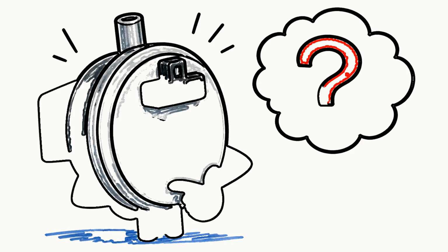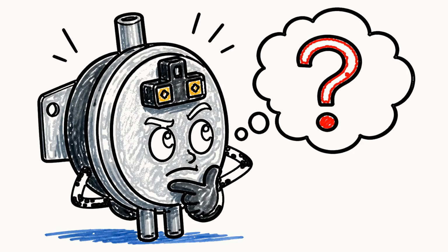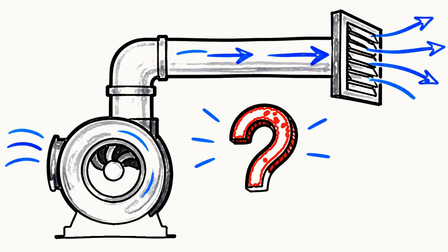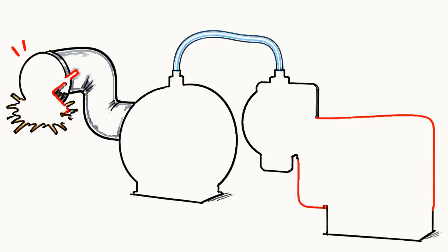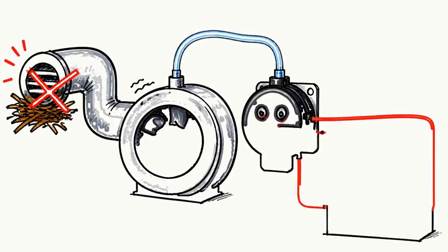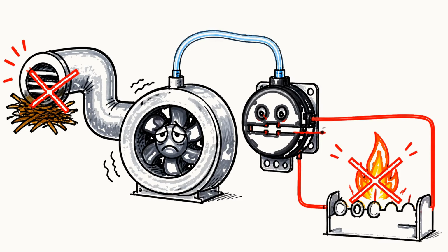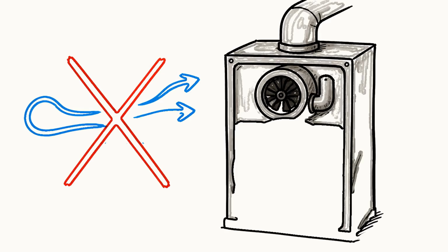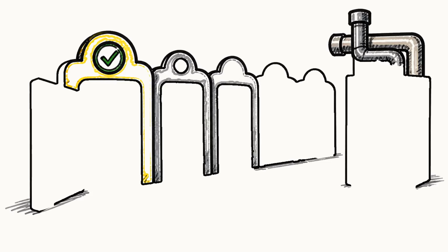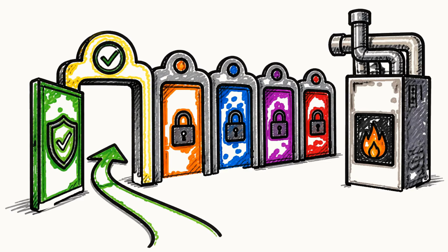The pressure switch is basically asking one question. Is air actually moving the way it should be? If the vent is blocked or that inducer fan is weak, the switch stays open and the furnace simply refuses to light. No proven airflow, no fire. It is the first of several safety gates the furnace will not skip.